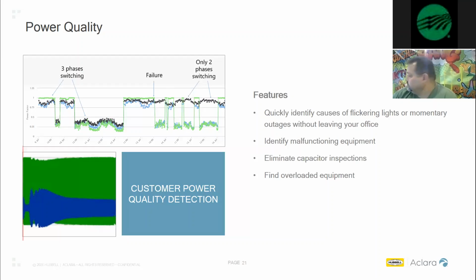So this all ties back to what we had mentioned earlier when Gary talked about the slides of the arcing faults and overloaded transformers. All of these types of events are causing disturbances that the sensors and SMS can help identify. Typically, like we said, the SCADA system, if you have it in place, might not pick up these minor disturbances that are happening. However, these disturbances to us are extremely important to identifying things that could proactively turn into anomalies that could be faults down the road, sustained faults, or even sustained outages. Being able to detect these early signs of disturbances and putting them into some type of rule base, as we call it, which I'll get into in a second, helps the user keep track of these happenings. It also lets them know that if we can collect a number or series of these, it could be leading to something that we want to pay attention to before it turns into some catastrophic fault or outage condition. So go ahead to the next one, Garrett.